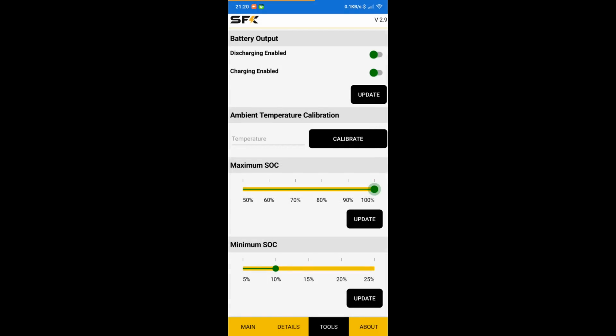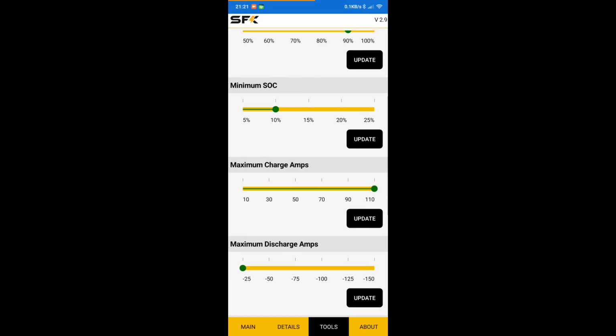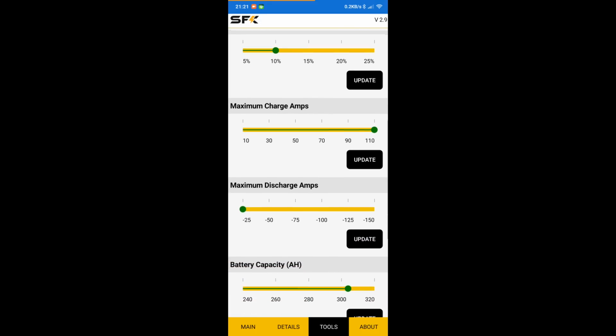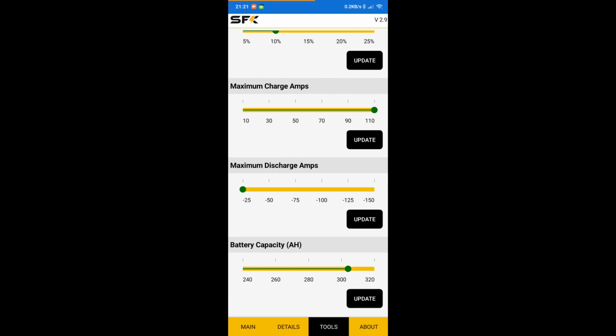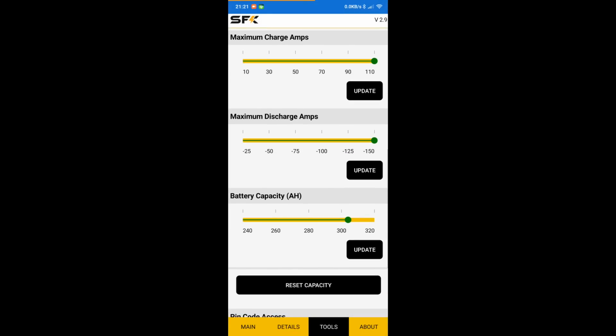We can set a maximum charge. How does this work? In percentage. How is it determined, 90%? Maximum charge amps 110, maximum discharge amps minus... Okay, so we can set this one to 150. Update. And the battery capacity is on 304. Update.